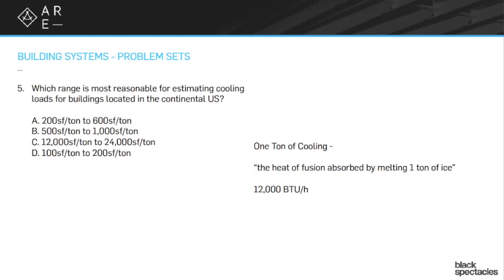You might think that's a big range — what's up with that? Well, if you start thinking about it, let's say we're talking about a thousand square feet of space and it's just like a simple, straightforward house. There's not a lot of people in there, not a lot of activities — cooking, people walking around — but not a big number of people. So I'm not going to have a giant cooling load generated by the number of people. And if there are a lot of trees giving shade, I'm not going to have a giant cooling load from solar radiation.